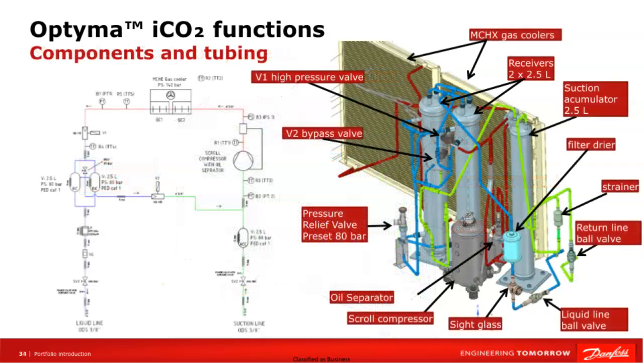On this slide, we can see how the rest of the elements are arranged in the condensing unit. Physically, looking at the real unit, most of these components are insulated and packed together, making them difficult to see. That's why such drawings are extremely helpful. On the left, we see the diagram, and on the right, we see the physical arrangement of the components. In the diagram and in reality, we notice elements such as the MCHX microchannel exchanger, bypass and high pressure valves, safety valve, compressor, liquid receiver, filters, and ball valves.